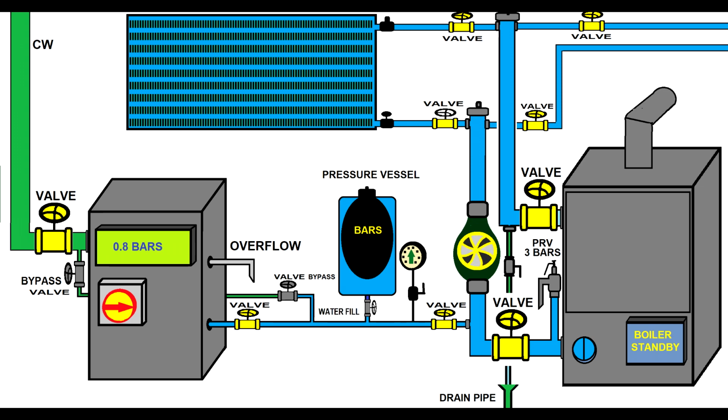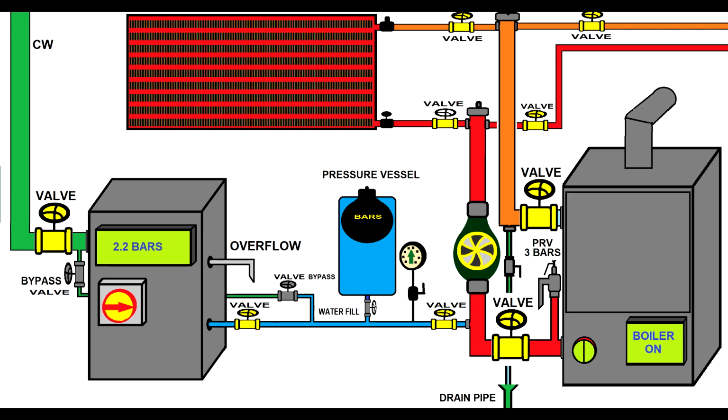I want to make sure all the air will be eliminated through these air eliminators. There could be pockets of air in some places, and I just want to make sure my installation is properly filled and I don't have air in the installation.